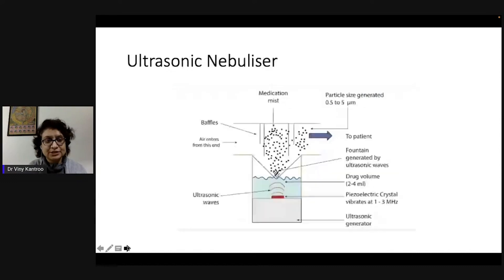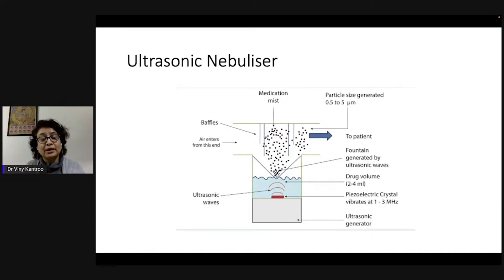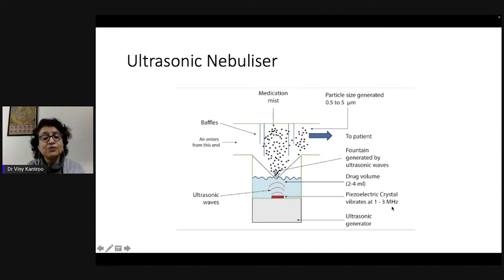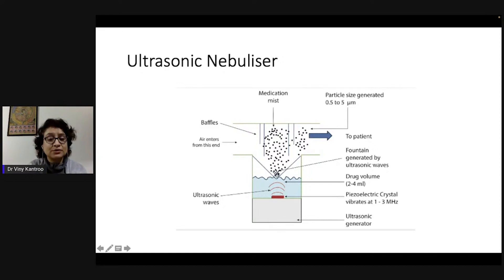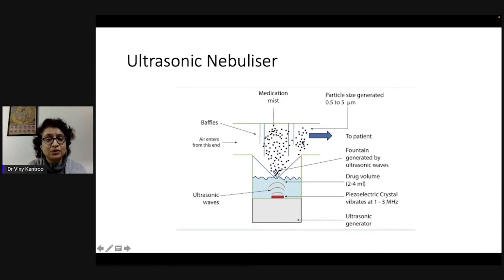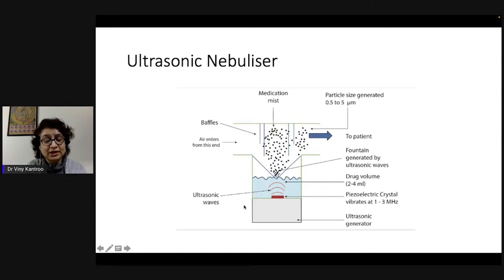Ultrasonic nebulizers are a step more advanced. They have a piezoelectric crystal at the bottom that vibrates at a rate of one to three megahertz, creating vibrations in the liquid. These ultrasonic waves are responsible for converting the liquid into aerosol form. Particle size varies between 0.5 to 5 microns. A key advantage is that ultrasonic nebulizers are virtually noise-free.